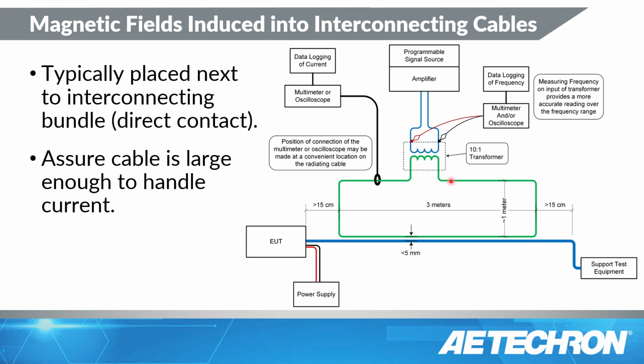What I like to use in this case is 12 gauge speaker wire. This is the reason why I like to use it. First off, speaker wire tends to be very flexible, so I can wrap these wires next to or lie them next to this cable and still move them around easily enough to whatever position the transformer is. And the beauty of speaker wire is that it's what we also call zip cord. It has two conductors internally. And so now you have two current carrying conductors, both capable of carrying about 20 amps or so. And maybe you can get up to 30 amps with some caution because that cable's going to get hot. Remember that. And maybe you have to wrap it twice. So come around here, bring it over, back up, and do a second turn.